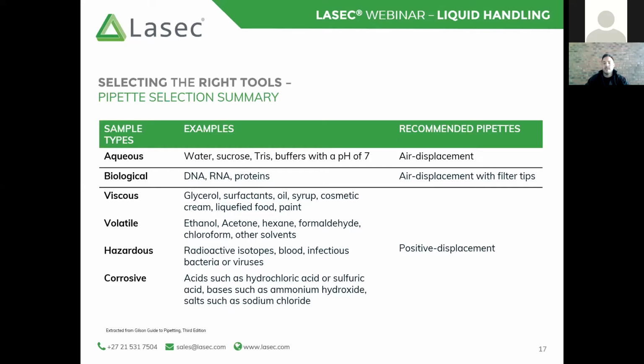Like I mentioned a bit earlier in this webinar, if you consider the air displacement pipette, in that microenvironment there's still room for the acetone or the ethanol to vaporize or evaporate into that air pocket, thereby changing the pressure inside the pipette. Those individuals who have been pipetting for quite some time would have noticed that what we experience with an air displacement pipette and volatile samples is a lot of leaking and dripping from the tip. This is simply because we cannot maintain that partial vacuum inside the tip as the solution starts evaporating. However, that issue is alleviated by using a positive displacement pipette, because now we no longer have an air cushion. It is a physical barrier, so there is no room for that volatile solution to evaporate any further in the tip. This will eliminate the leaking.